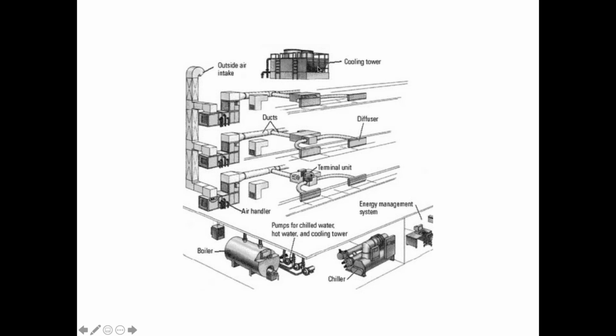So inside these cooling towers, they have makeups, they run continuously. The whole time the cooling tower is running, you're putting water into this cooling tower. But you're only throwing away 1% of the water, not 100% of the water, so you can reuse it. That's great, except that you're blowing air through that water, and that water that's spraying down is scrubbing organic material, bugs, pigeons, pollen, mold out of the air into your cooling tower water. And it's also oxygenated. So you got to deal with that water.